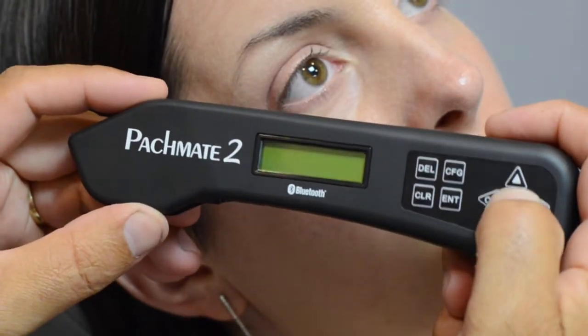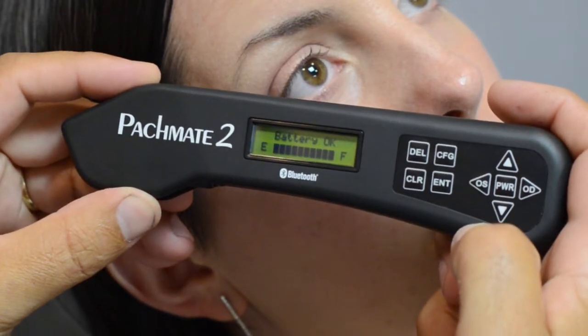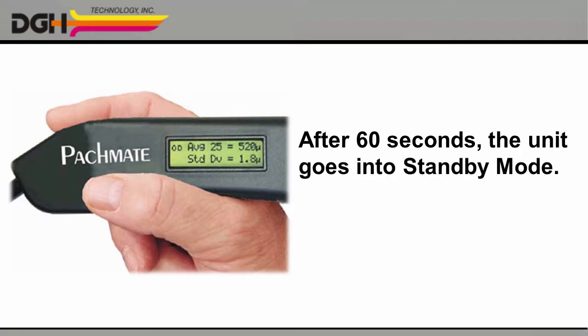Next, press the power button to turn on the unit. The Pachmate 2 will automatically run a self-diagnostic. If all's well, it will show you the status of the rechargeable battery, and then it will prompt you to begin measuring the patient's right eye. Please note, if you do not begin taking measurements within 60 seconds, the unit will automatically go into standby mode to save the battery.